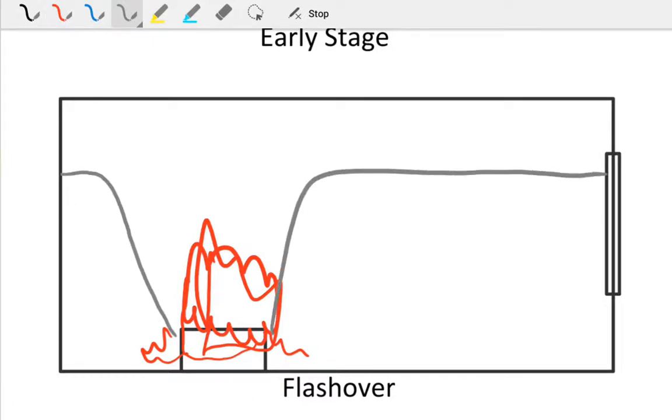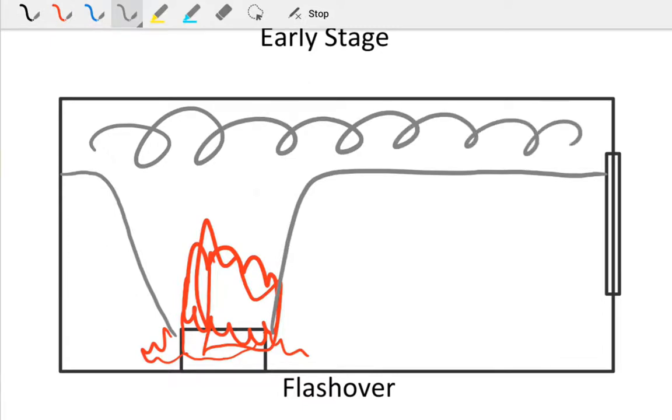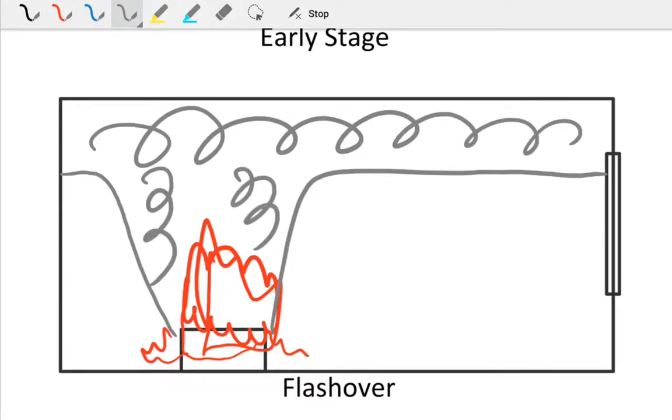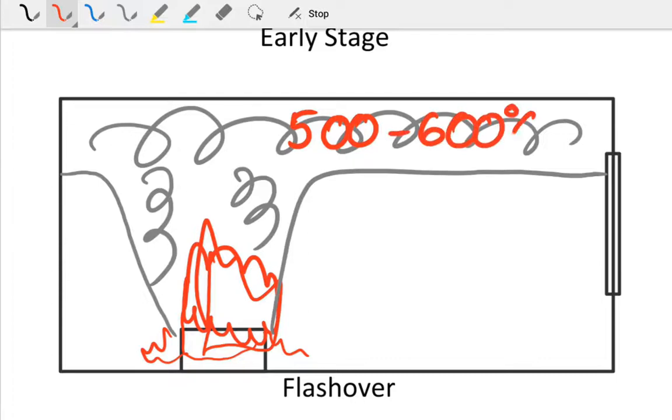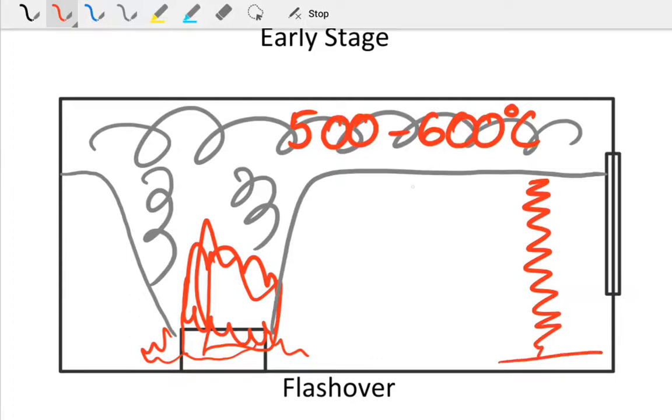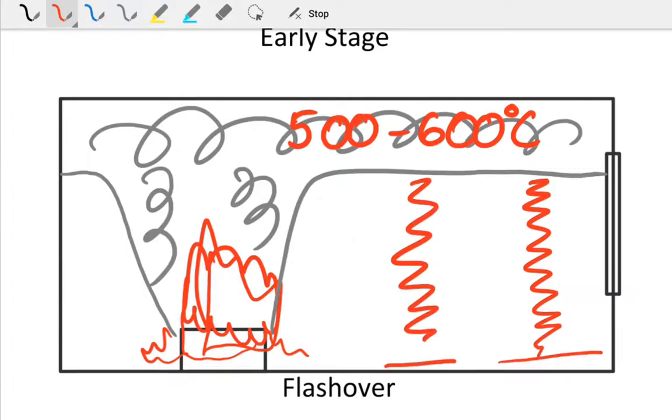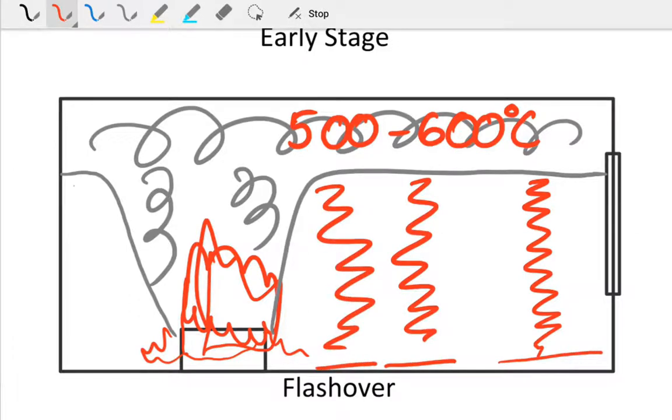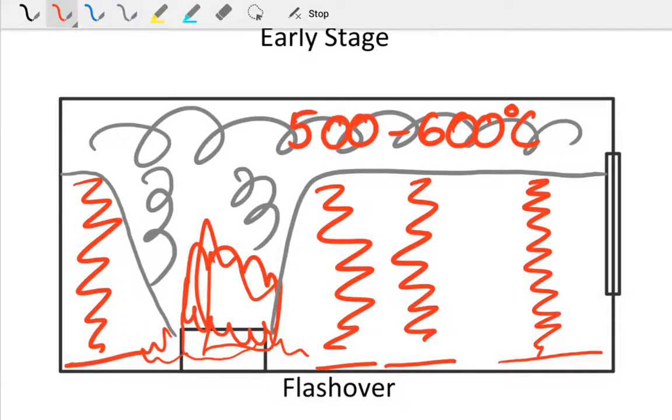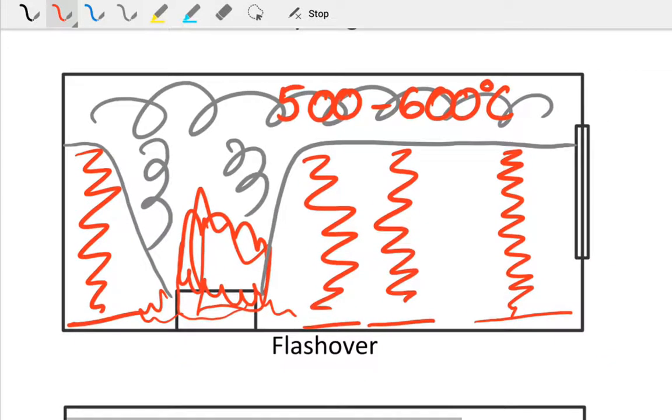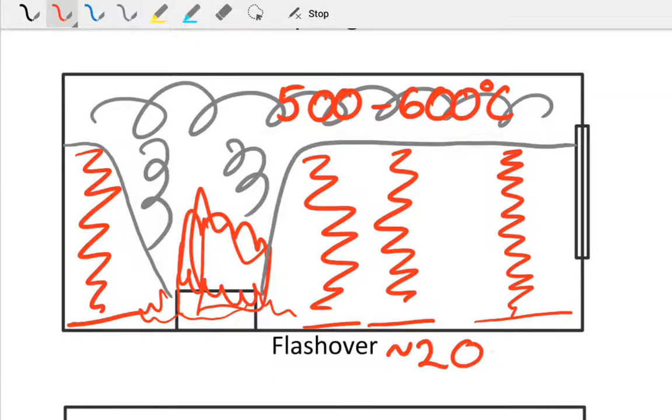Now our smoke layer is deeper. It will be in the vicinity of around 500 to 600 degrees Celsius. At this stage, you've got electromagnetic radiation, so you've got radiation down onto the floor. The radiation from the hot layer causes everything to spontaneously combust.